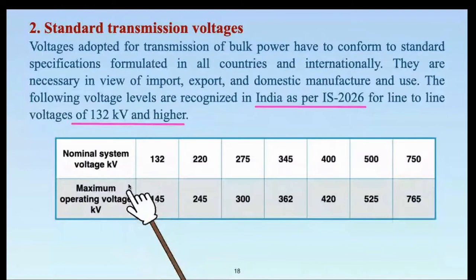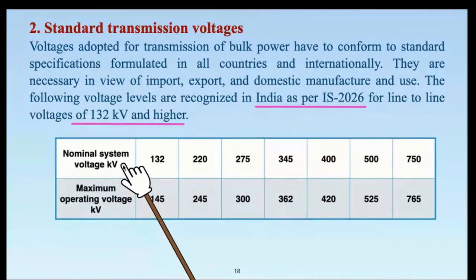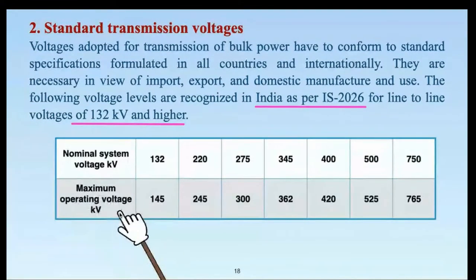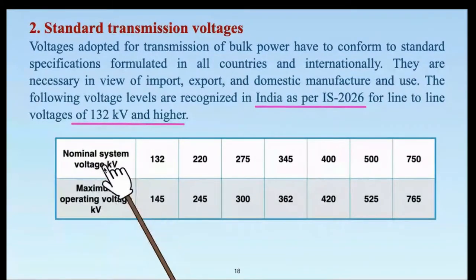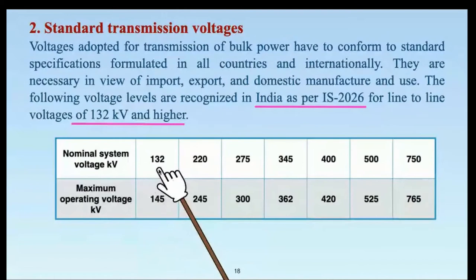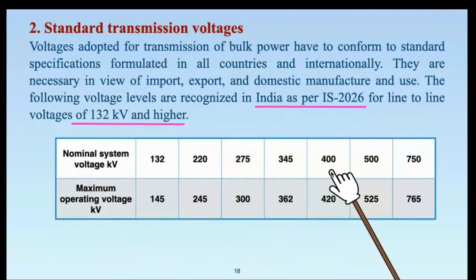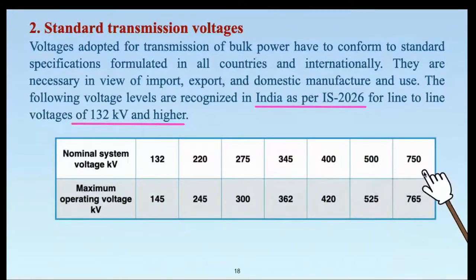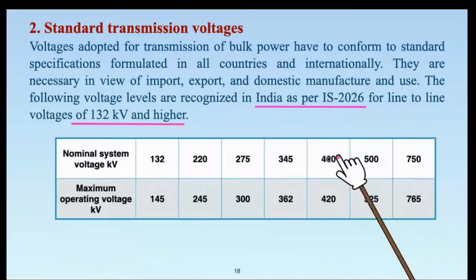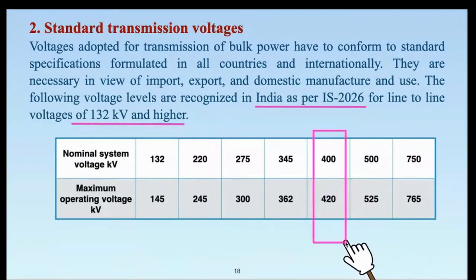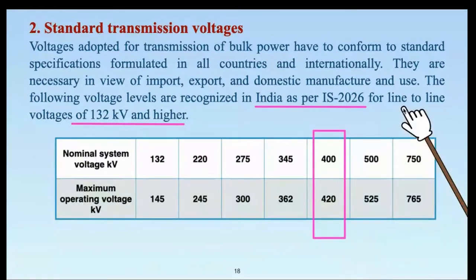The first domain is nominal system voltage, also known as the rated transmission voltage for the transmission network. The second is the maximum operating voltage — the highest value of voltage the system will be able to carry while handling power. Nominal system voltage levels in India are: 132 kV, 220 kV, 275 kV, 345 kV, 400 kV, 500 kV, and 750 kV. The most common long-distance transmission voltage is 400 kV.